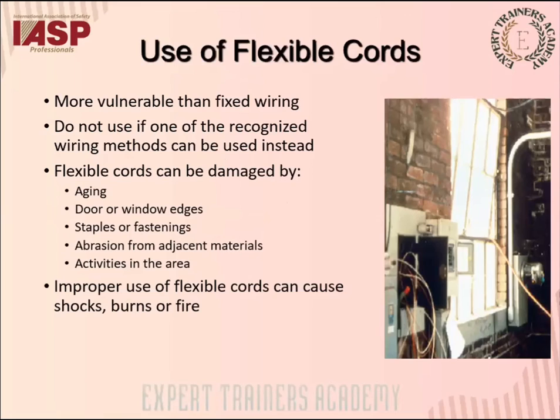So, use of flexible cords. They are more vulnerable than fixed wiring. Do not use them if one of the recognized wiring methods can be used instead. Flexible cords can be damaged by aging, the number of days that you've been using them. They can be stuck in window edges or door edges. They can be damaged by fastening. They can suffer abrasion from adjacent material. It may lead to chemical damage. Chemical corrosion may occur on the insulation.